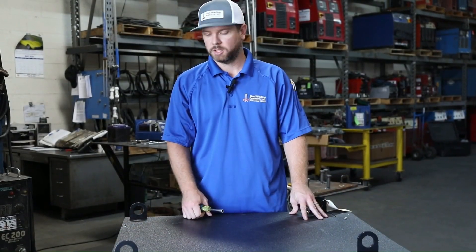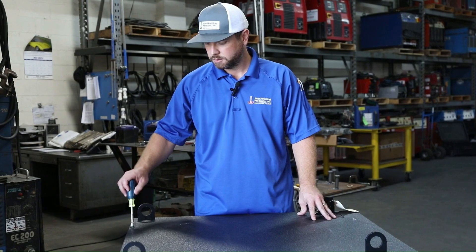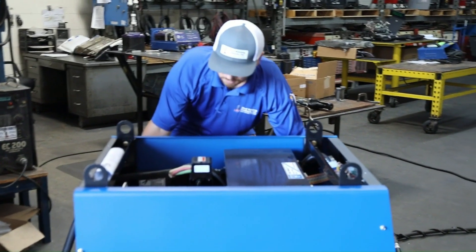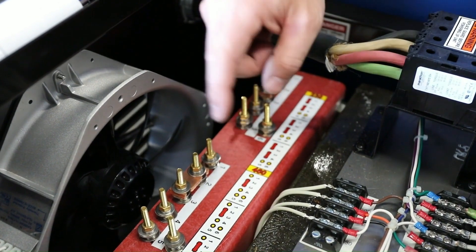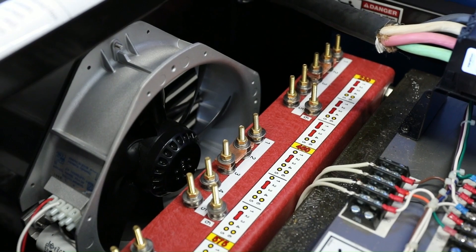Check to make sure we have the correct input settings for the power. We're going to take a 3/8 nut driver and remove the four screws on the top. Once you've removed your screws, make sure you are disconnected from power. This machine is capable of running on 230, 460, or 575 three-phase. Reference the chart here for the tap orientation.